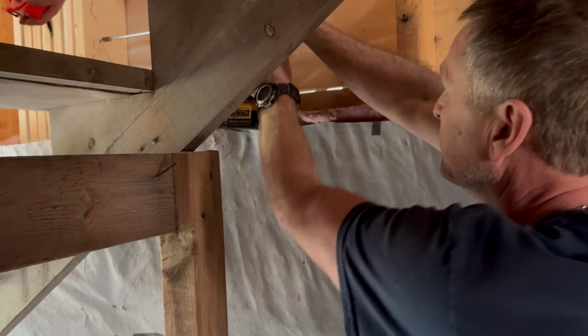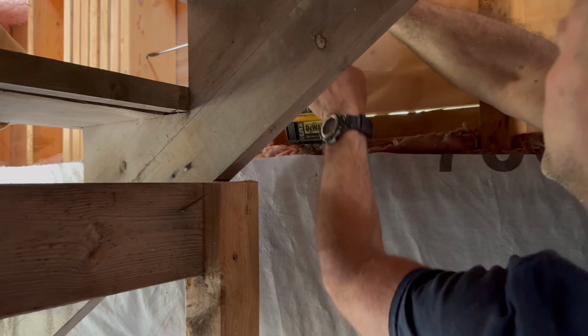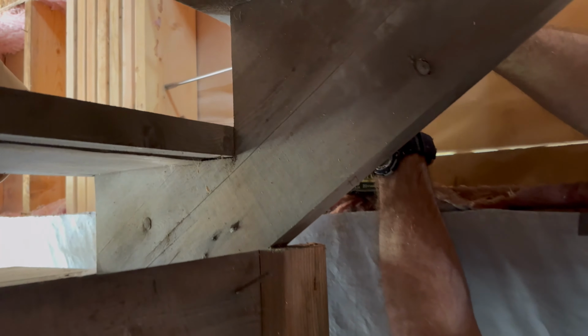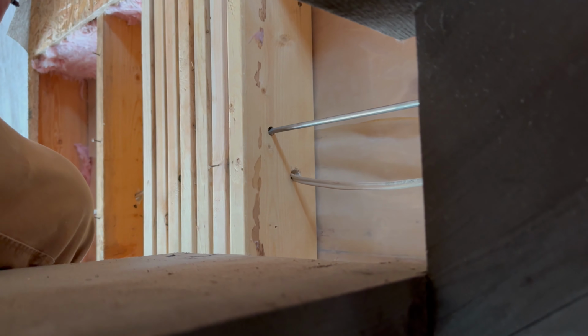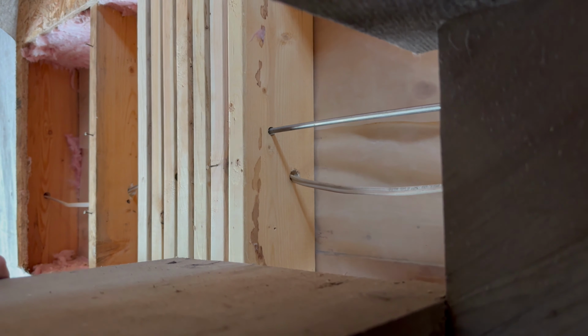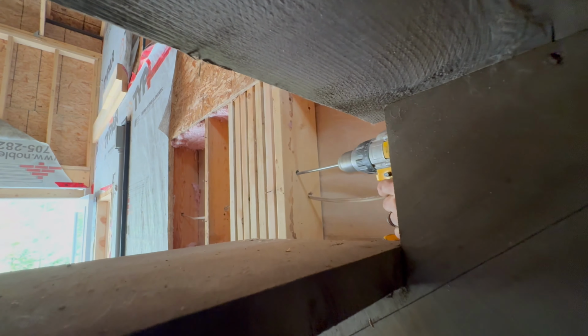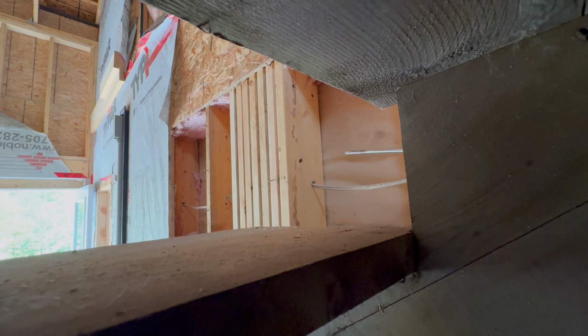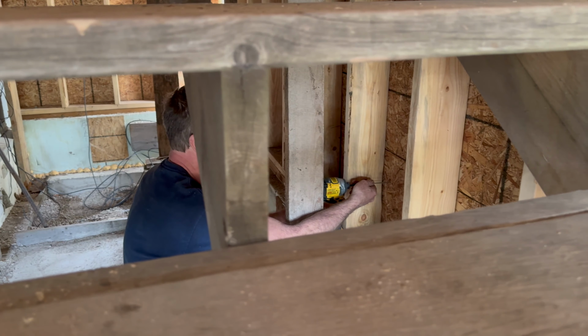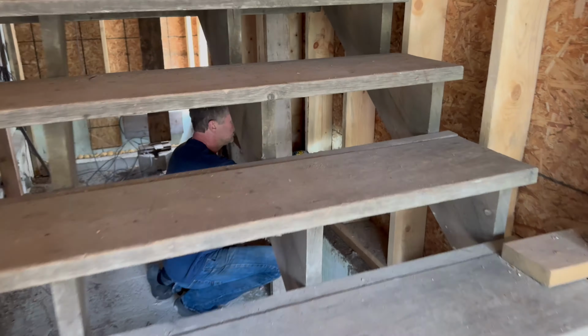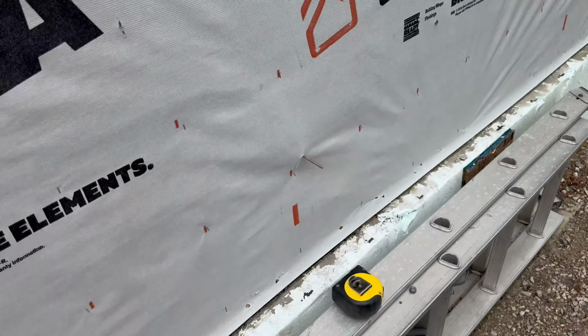Now it's time to switch gears a bit. Brad's boring some holes through framing members to run the other leg of heavy cable. This will connect the transfer switch panel to the outdoor inlet that the generator will be connected to during an outage. This is just a screw to mark the location. One great way to know where you need to drill a hole for this outdoor inlet is by driving a deck screw from the inside out to mark the spot.